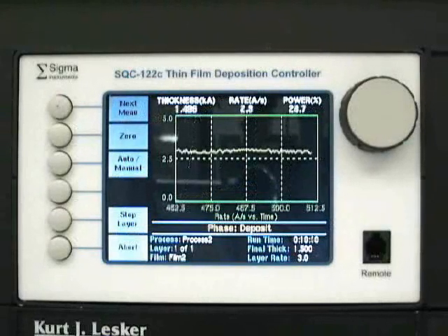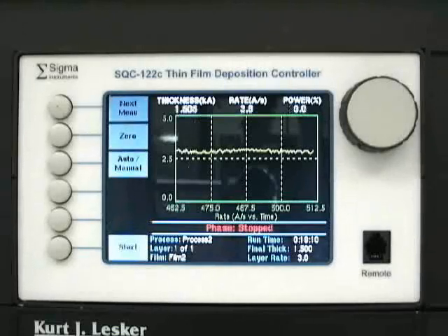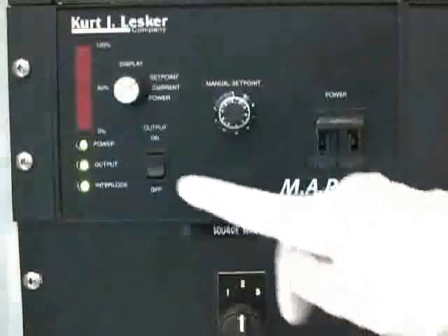Once the first metal has been evaporated and you are planning to evaporate more than one type of metal, set the deposition monitor to the next metal type and select the appropriate electrode pair on the source selector. If you have completed your process run, turn the filament power switch to off.